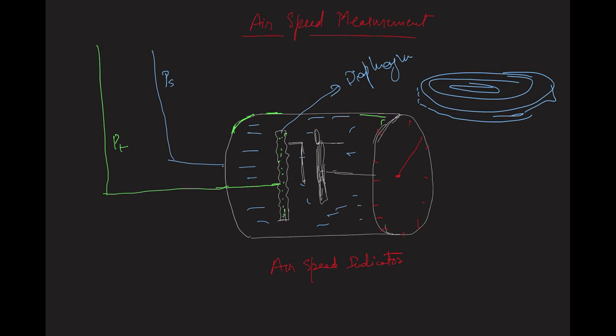The static pressure line enters the casing and fills the area around the diaphragm — indicated by the blue region. So all this blue area indicates the static pressure. Inside the casing we have static pressure, and inside the diaphragm we have total pressure. The diaphragm therefore experiences total pressure from inside and static pressure from outside.